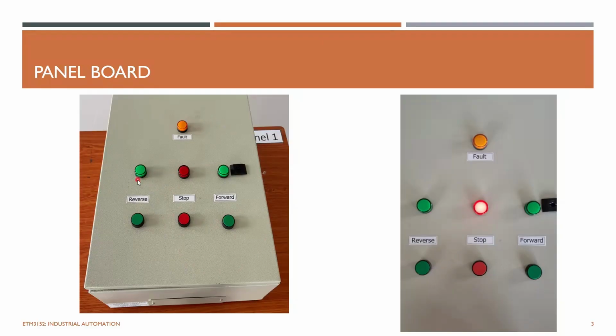So here we have these light indicators. When you turn on using the reverse push button, the green lamp for reverse running will light up, and for the forward running also we have another light indicator. When you stop the motor, by default it should look like this, the red color light comes up.